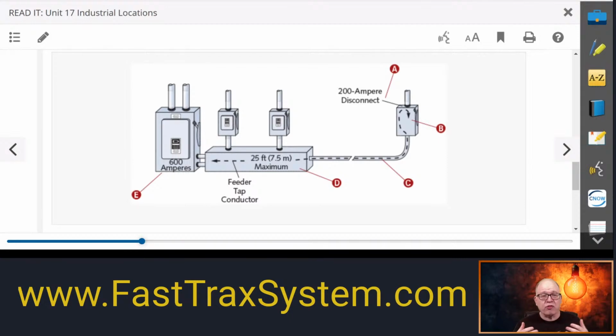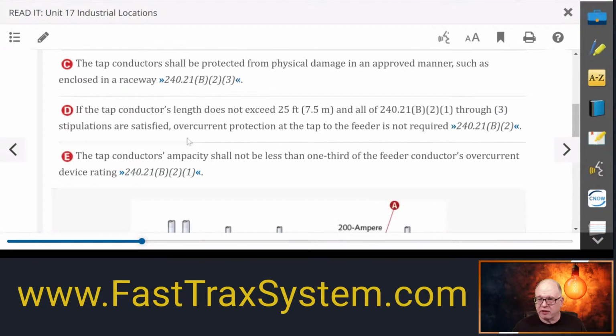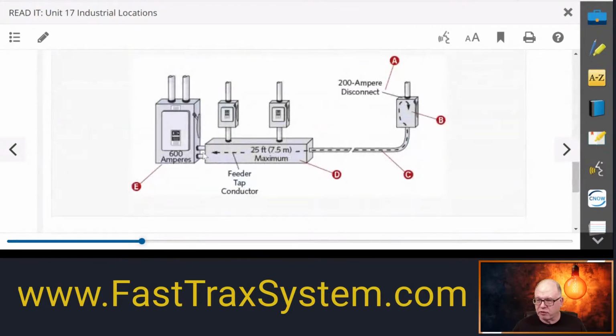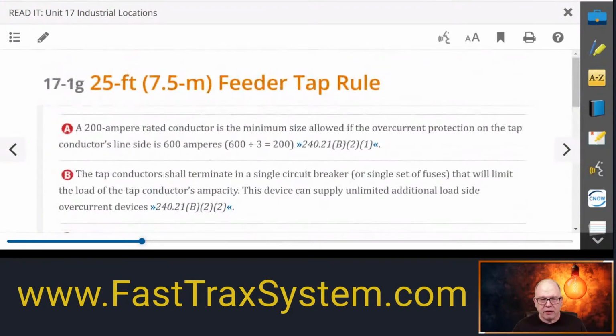And the tap rules simply mean that the tap conductor I'm tapping on does not have the same ampacity as the feeder that it's tapping onto. And the code allows this. Okay, so the maximum distance in this case is 25 feet. All right, so let's go back and let's kind of pick this picture apart.